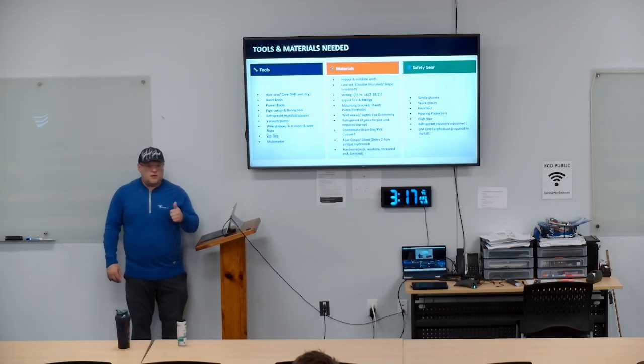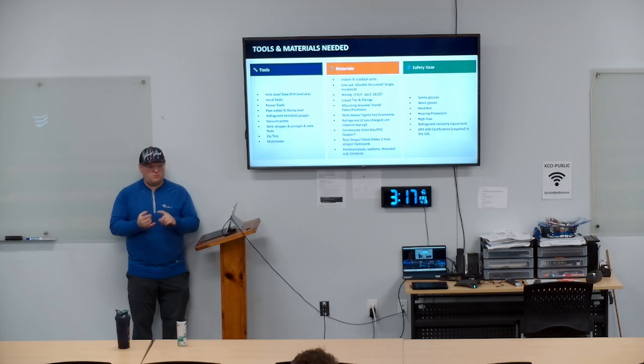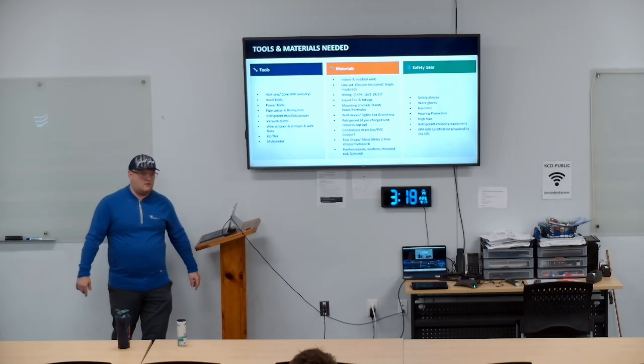Wall sleeves and the little white exit grommets, they're called Seegers exit grommets. So if you didn't know that. Wall sleeves, we should be sleeving brick. I mean, metal. The reason I say metal is because if it's sharp, it's going to cut the insulation. It's going to cut that pipe. You're not going to notice it as much, but when that pipe is sitting there attached and the compressor's running, if we're 5 foot away from the building, that compressor is going to vibrate that copper a little bit. And if it's touching that metal over time, that metal is going to cut through the copper. Then we're going to lose refrigeration. We're going to be screwed. Okay, cut this, pull it out, redo it. So these are why we're doing this stuff.